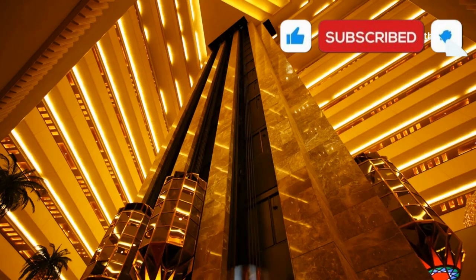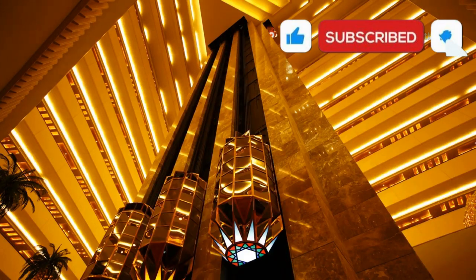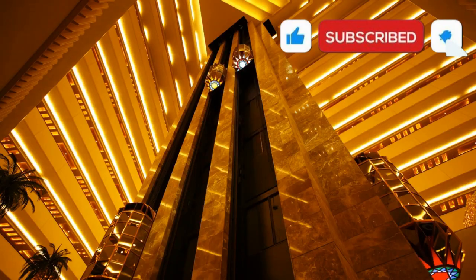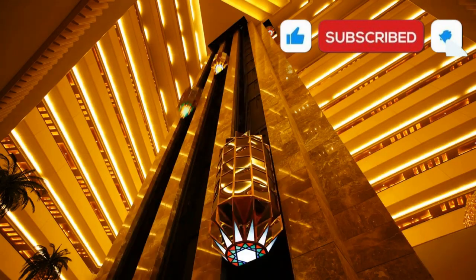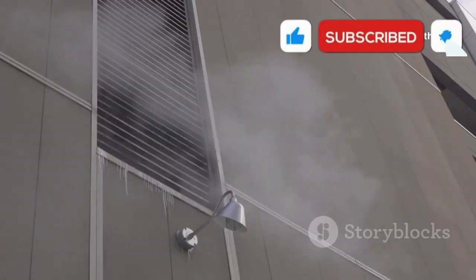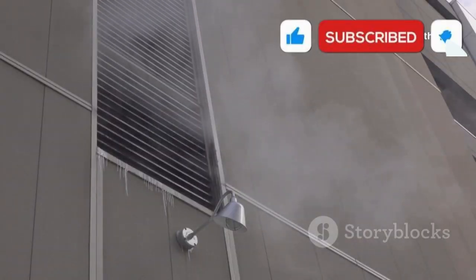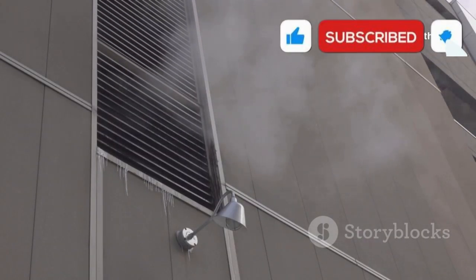There's also the stack effect. Warm air rises, creating a chimney-like flow up elevator shafts and stairwells. This can make upper floors even hotter and complicates cooling. Engineers have to design systems that counteract this effect and keep temperatures even from top to bottom.